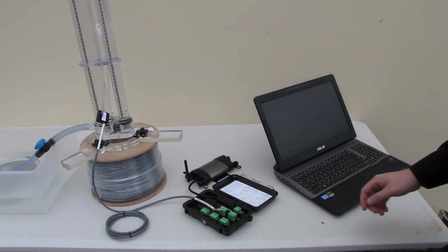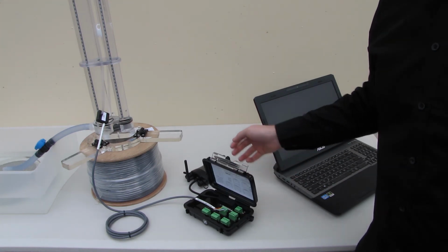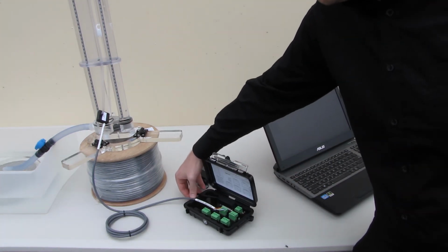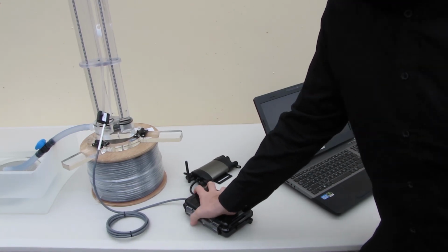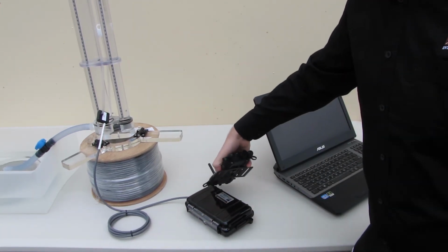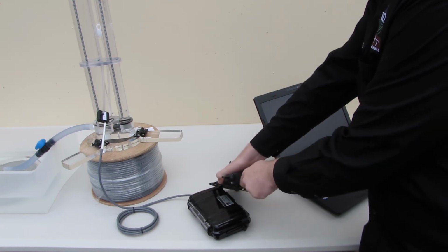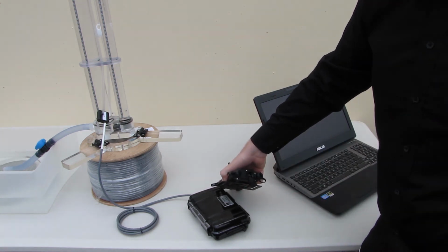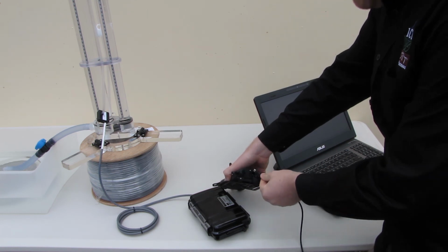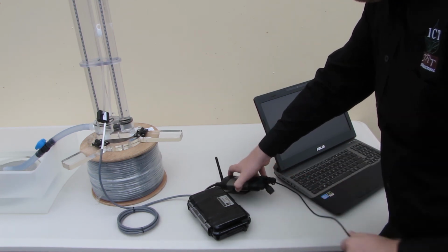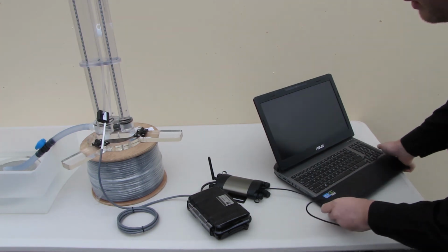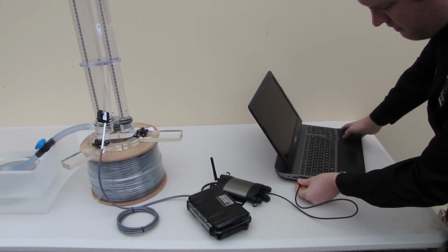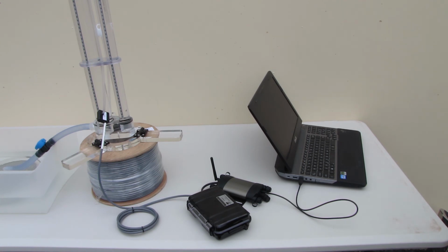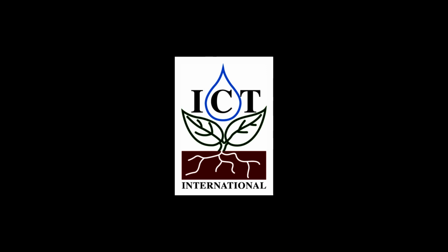Here is an example of connecting the computer ready for setting up the instrument. Place the AIM1 logger cable into the waterproofing seal and close the breakout box lid. On the AIM1 logger, gently unscrew the entire USB port cap, exposing the power button, USB connector and SD card. Connect a mini B USB cable into the AIM1. Plugging in a powered USB connector to any ICT logger will power it up automatically. You are now ready to set a logging interval on the AIM1 using the ICT Combined Instrument software.